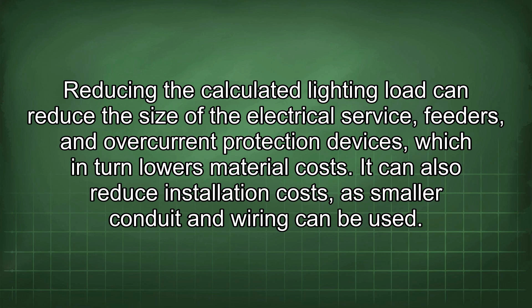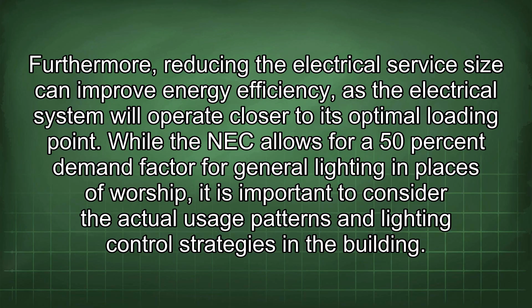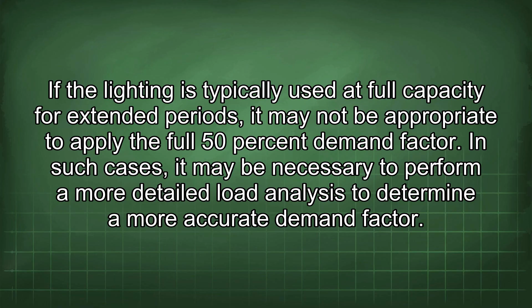While the NEC allows for a 50% demand factor for general lighting in places of worship, it is important to consider the actual usage patterns and lighting control strategies in the building. If the lighting is typically used at full capacity for extended periods, it may not be appropriate to apply the full 50% demand factor. In such cases, it may be necessary to perform a more detailed load analysis to determine a more accurate demand factor.